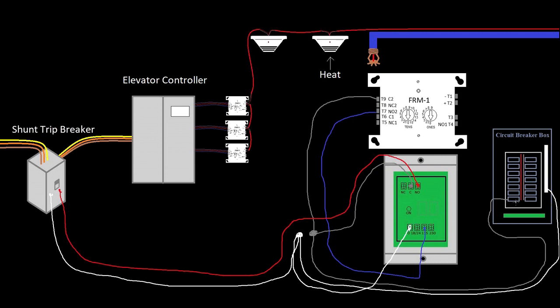So it's required that that shunt trip power is monitored, and since it's a 120 volt circuit we don't really have a way of just throwing a monitor module on a 120 volt circuit. So we need to utilize another relay just like we did to activate the coil of the shunt trip breaker. We need to use another one of those relays to be activated by this power at all times to make sure it stays on, and then land a monitor module on that to make sure it doesn't change states.